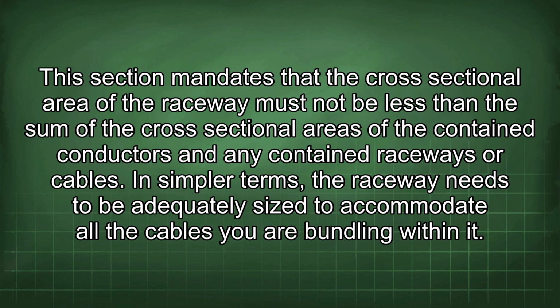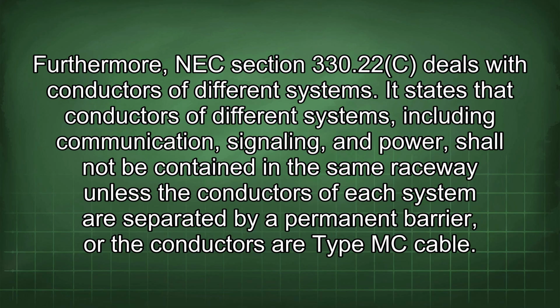This section mandates that the cross-sectional area of the raceway must not be less than the sum of the cross-sectional areas of the contained conductors and any contained raceways or cables. In simpler terms, the raceway needs to be adequately sized to accommodate all the cables you are bundling within it. Furthermore, NEC Section 330.22c deals with conductors of different systems.